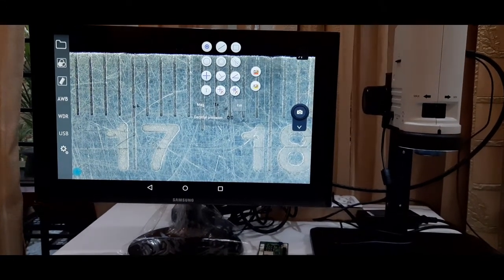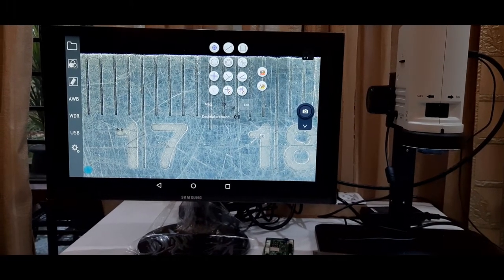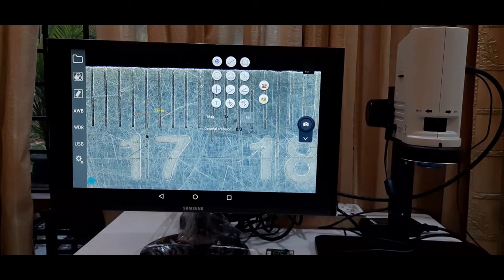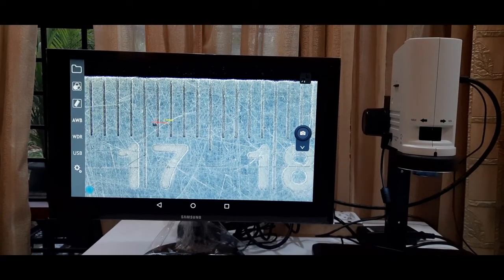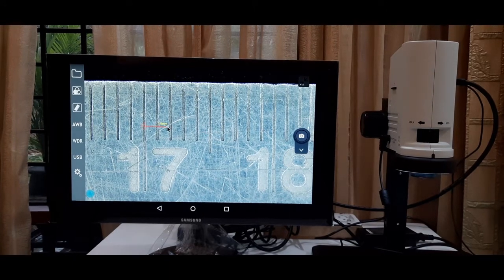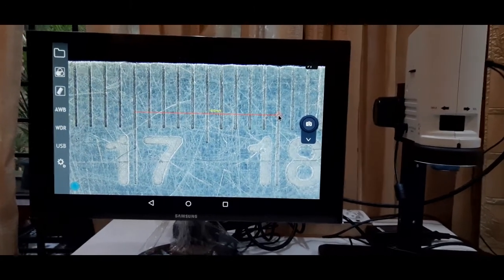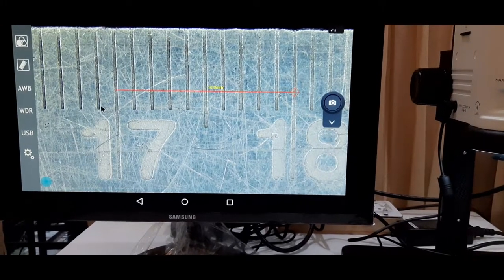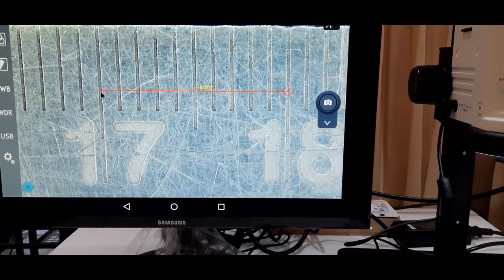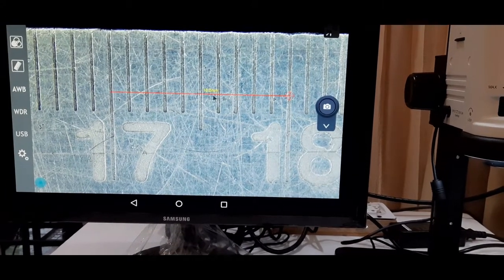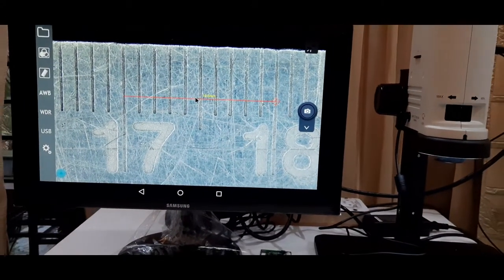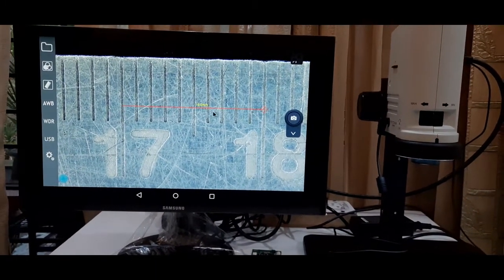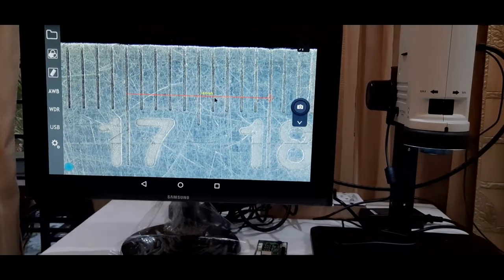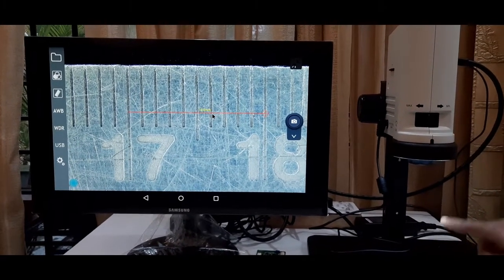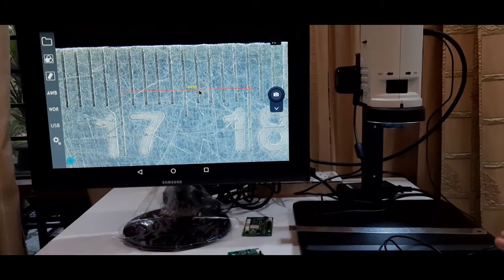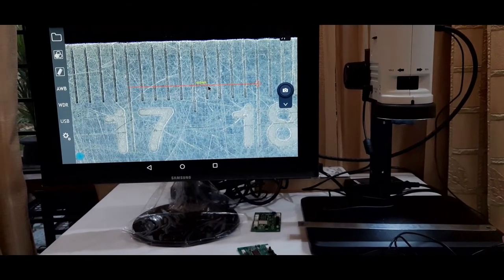And now we will again verify whether the calibration performed by us is saved or not, and we will measure a line, this line. See, now the actual value is 10 mm and the value after calibration, the magnified value, is also 10 mm. So this is how the calibration is done. And once we save this calibration, do not adjust this knob or do not adjust the working distance, otherwise the calibration will need to be done again.